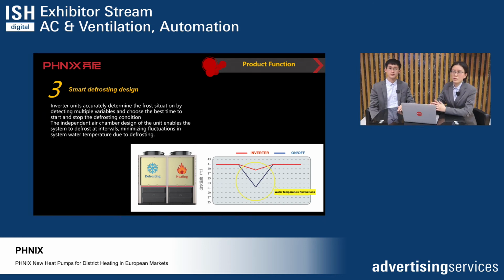And the third one is the smart defrosting design. You know, in northern China, northern Europe and other countries, in the winter season, the ambient temperature could be very low, very cold. Yes. There is always heavy snow and heavy frost. Correct. When there is so much heavy snow and frost on the fin heat exchanger, our heat pumps will start to defrost smartly. Good.